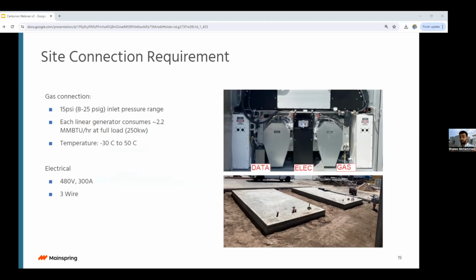The gas connection is 1-inch threaded pipe. We consume about 2.2 MMBTU at max rate. Roughly, we're just looking for 2 MMBTU from a consumption point of view, 1.9-ish. Flow could be a little bit higher than that. And we're looking for somewhere between 8 to 25 PSI, so 15 PSI nominal.